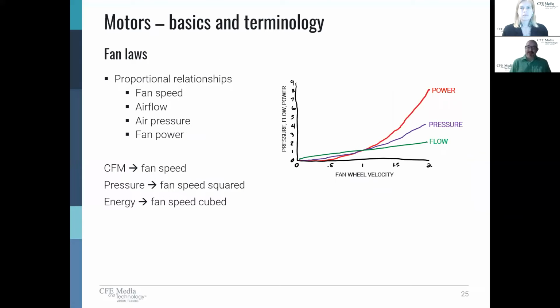Now, we got to get a little technical here. We're going to talk about fan laws. Now, fan laws are essentially the proportional relationships between speed, flow, pressure, and power. They always apply. So that means if I want to figure out, if I change one parameter, what happens to the other ones, I go to the fan laws. Electrically, we would consider Ohm's law and how power and current and voltage and resistance relate to each other. This is the mechanical analog of that.